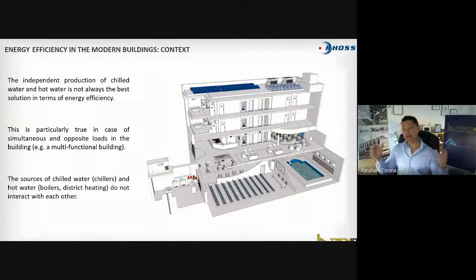That is good for Australia that now we're waking up. I remember when I started to promote EXP polyvalent pump, RHOSS is one of the pioneers. We have been doing it for 18-plus years, since the early 2000s. And 8 years ago, I started to talk with some consultants, some contractors, and they were not interested. First thing, we're used to using boilers. Second thing, until only a few years ago, we were still allowed to use even electric heating in your air handling unit in a building. I don't think now you can replace an old electric heating with another electric heating when you're doing a retrofit, but we still have many air handling units running with electric heating around. So now Australia is waking up, and this is the reason we're preparing this kind of presentation.